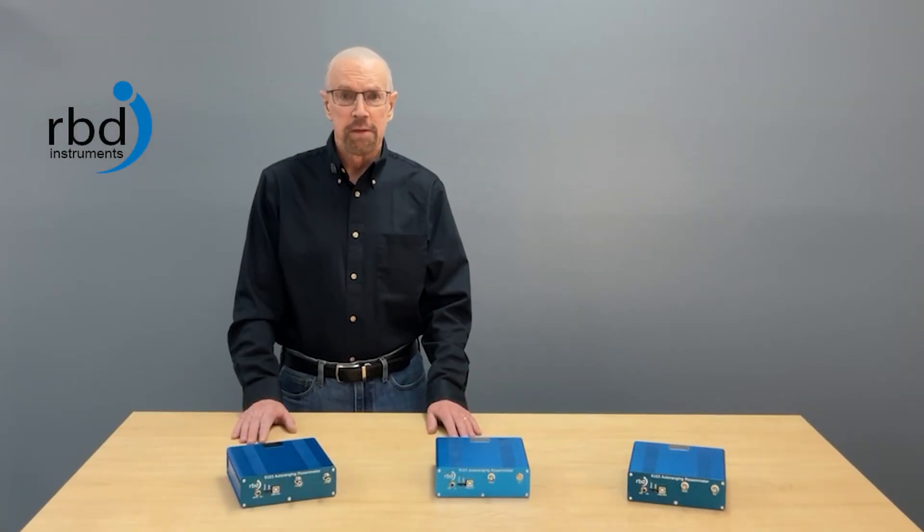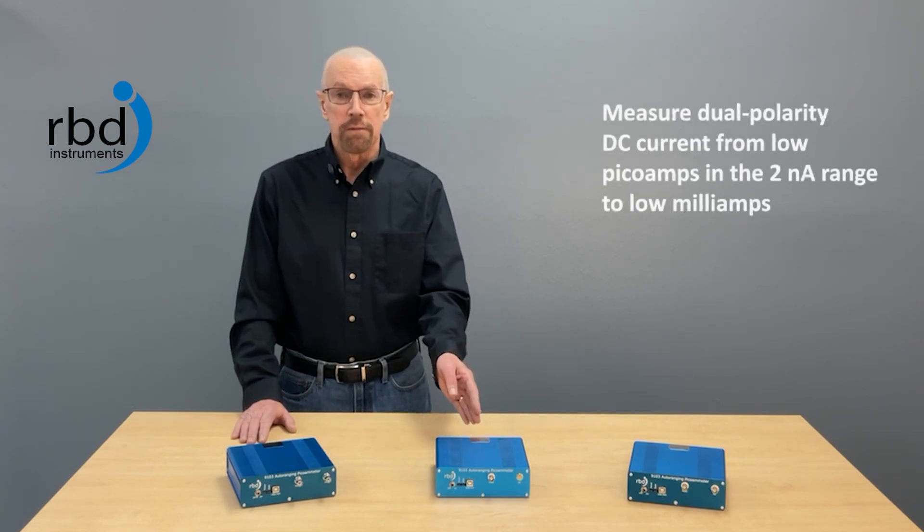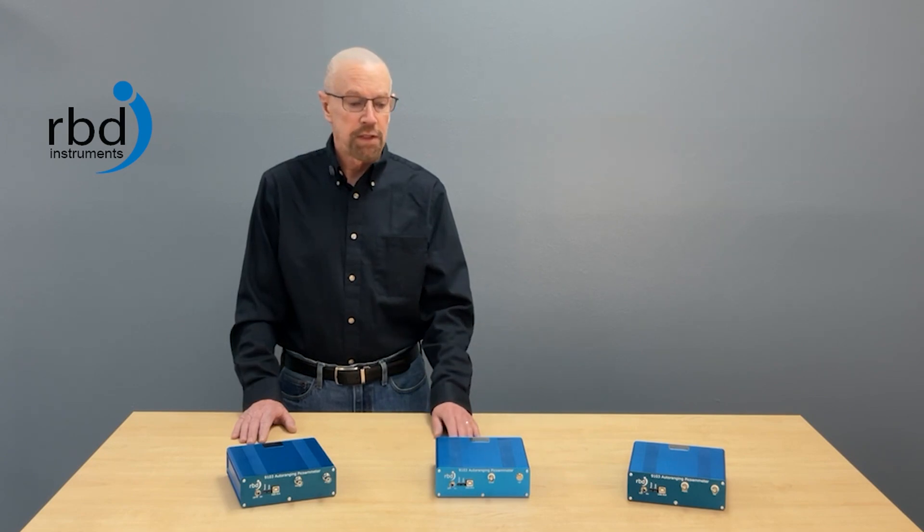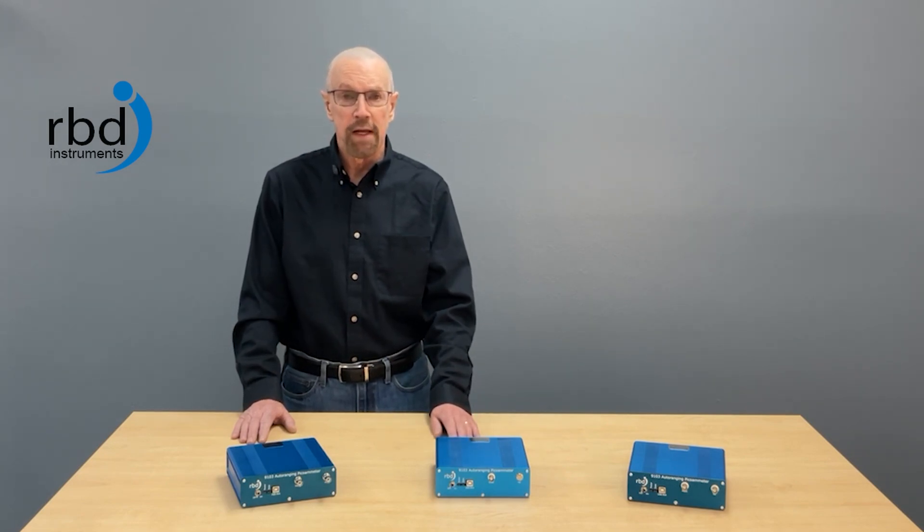Hi, I'm Randy with RBD Instruments and today we're going to talk about our 9103 USB picoammeter. The 9103 can measure dual polarity, low DC currents from picoamps to milliamps. As you can see, there's no panel meter on the 9103, but rather the data is displayed via your PC.